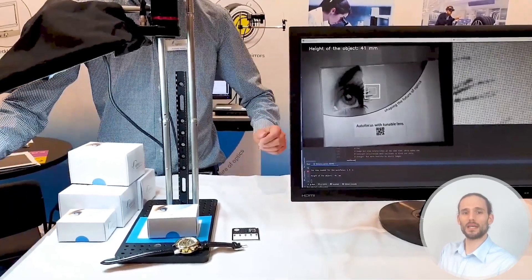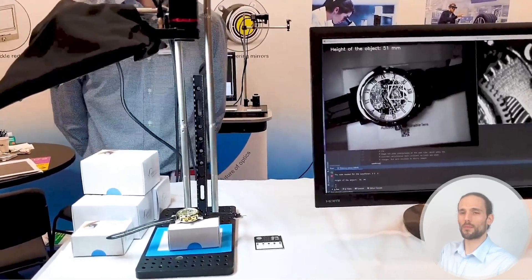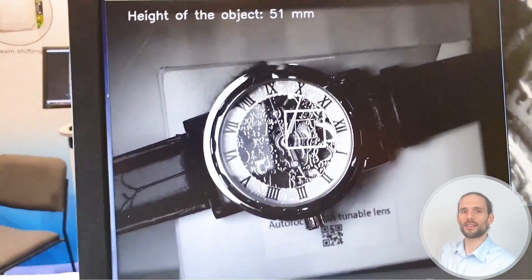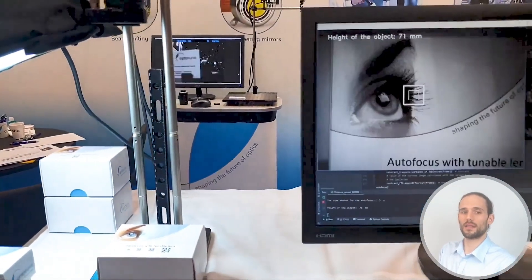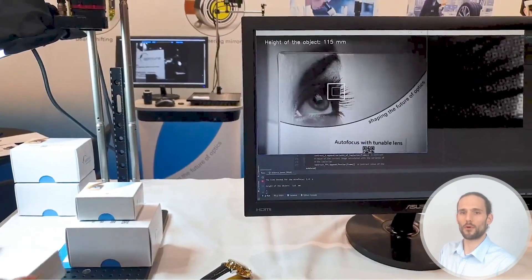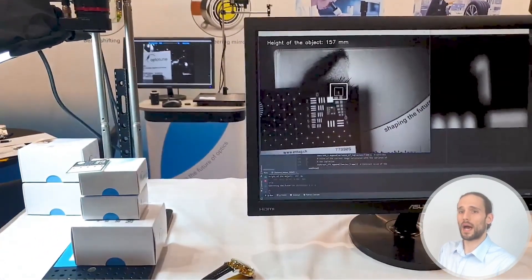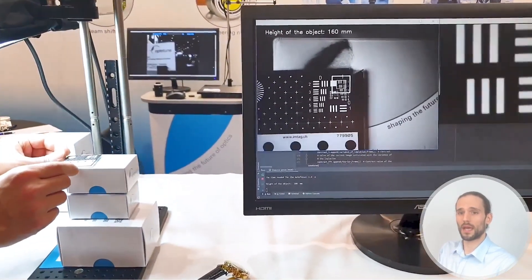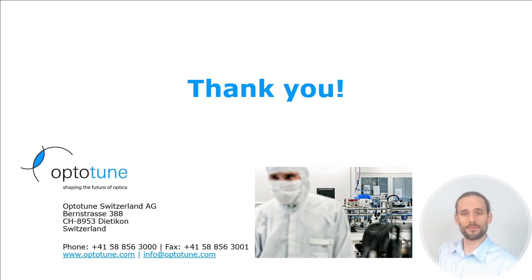And now you can see basically my colleague stacking up objects into the object plane. And you can see how reactive the software is, which basically first puts the image in focus and then reads out the distance of the object. Again, we can do this one more time, different objects stacking more and more. You see how fast this reacts. The height of the object updates within a second. And again, this works for different materials. The presentation is over. Thanks for watching. Take care.